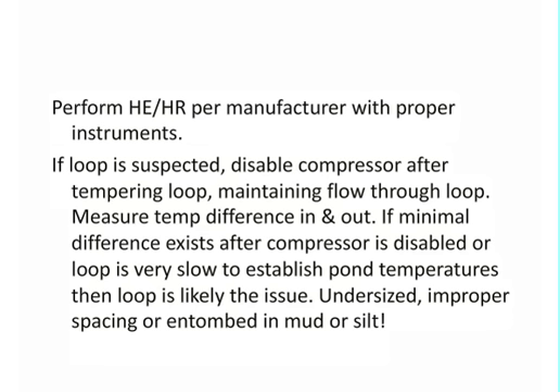So if you come across a project and you are finding that it's not performing, that's been the complaint, well, here's something you want to do. You want to consider doing what we call heat of extraction, heat of rejection per the manufacturer with proper instrumentation. Again, one pressure gauge, not two. One digital pocket thermometer through your PT ports. You want to validate that that heat pump is doing its all. You want to make sure you have at least a 15-minute run period so that the temperatures of the loop have stabilized, as well as the ducting if that's involved, and the refrigerant pressures have stabilized. You want to see what's truly going on.